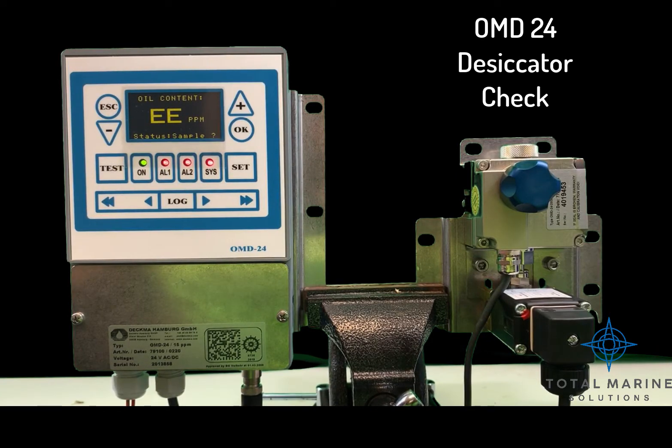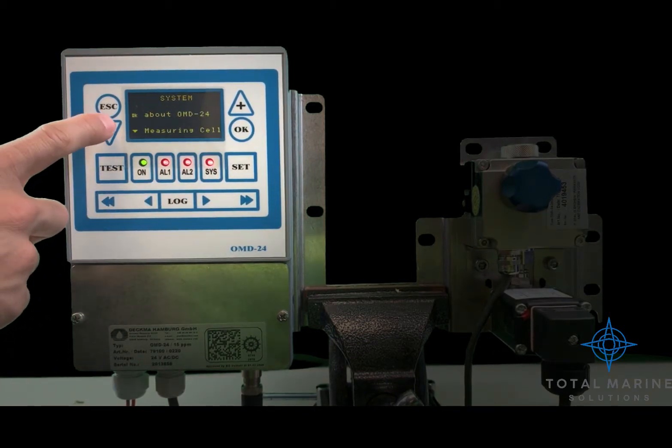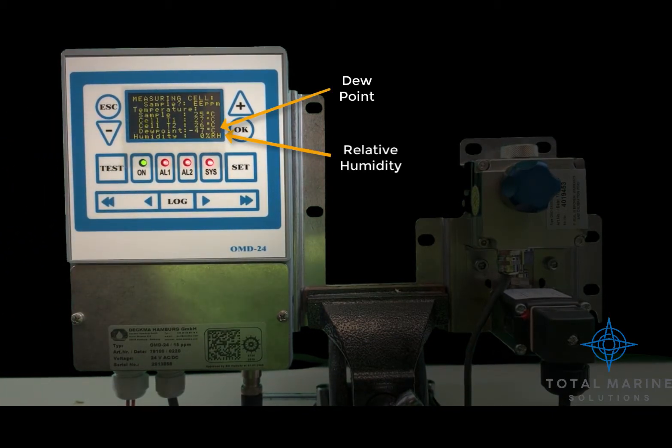OMD24 desiccator check. Press the SYS button, then press down to select measuring cell. The relative humidity should be below 10%. The dew point temperature should be below 0 degrees centigrade.